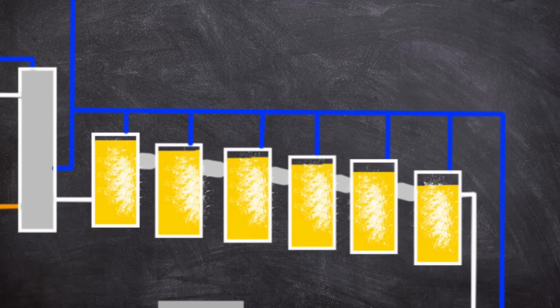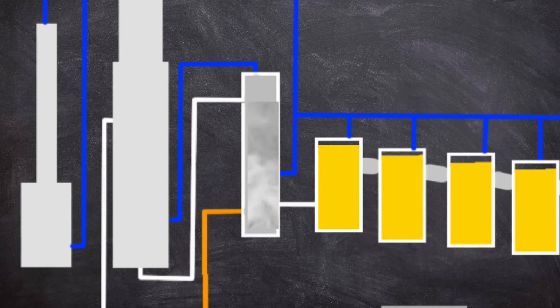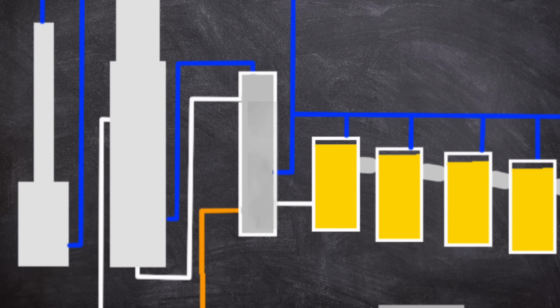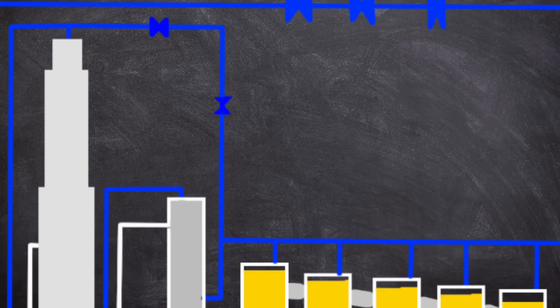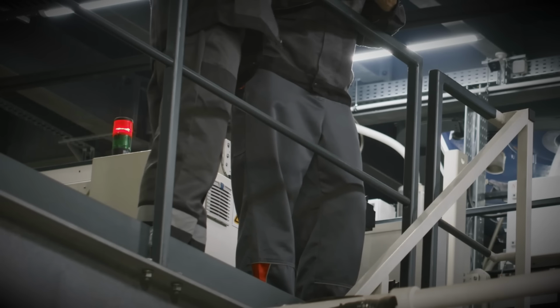By 12 PM, the process control technician noticed the pressure at a point where intervention was required. Reducing the steam yielded no result. By now, the pressure was at 9.2 kilograms per centimetre squared. The technician sent an operator out to open the block valve. This did get the pressure below 8.8. The system was in a pretty difficult state.